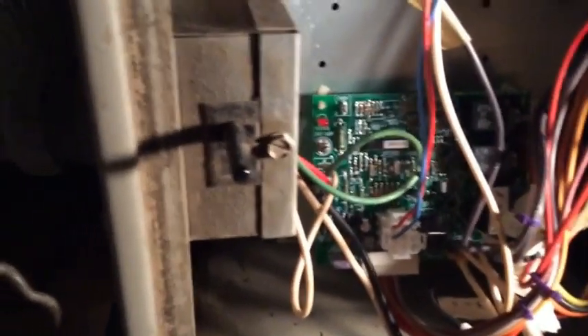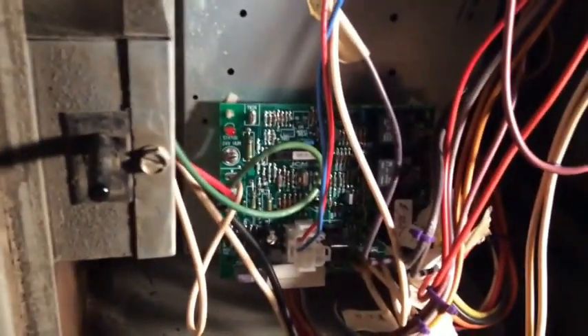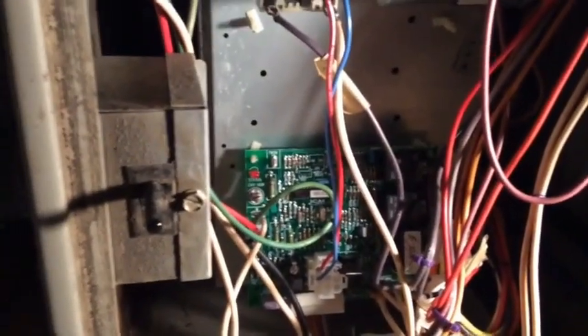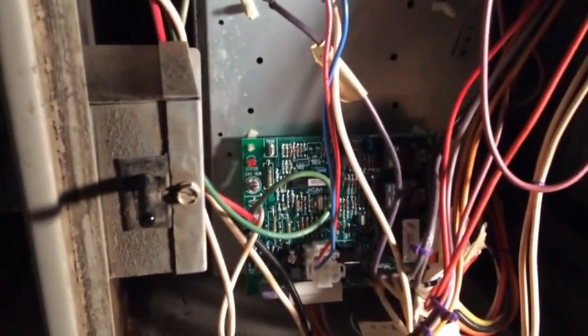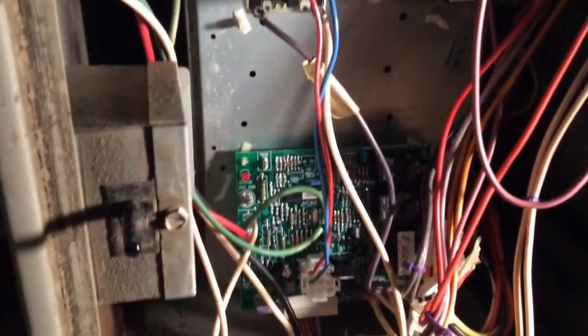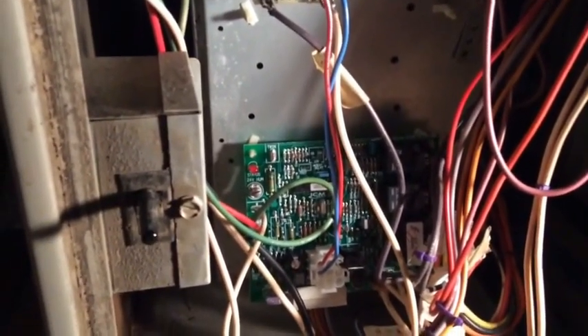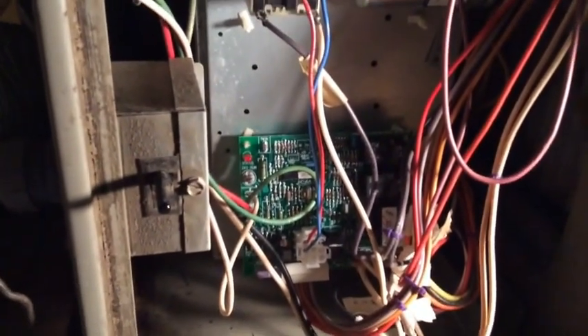The delay timer on the blower is set at 90 seconds, and that's default. Some units might have a different blower delay. In this case, it just stays the same. But anyway, let's get the power back on and the gas back on and test it out. Turn the power on at the breakers.